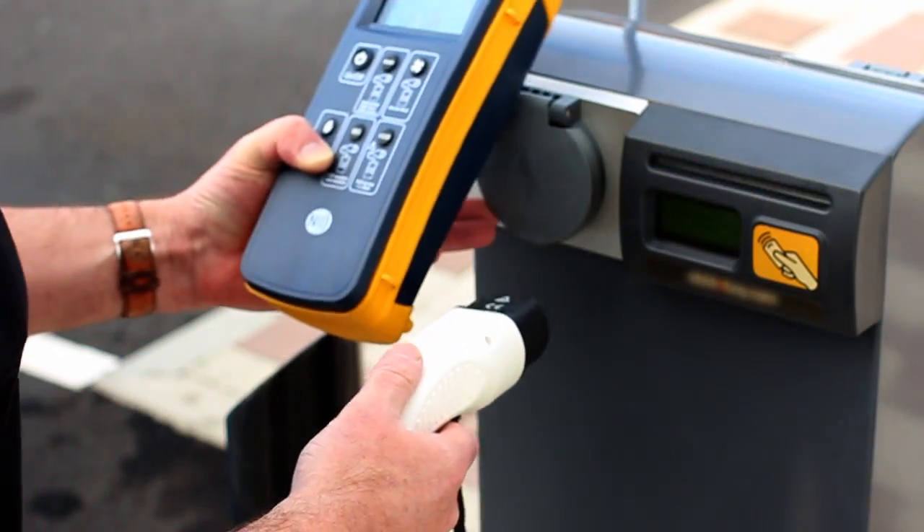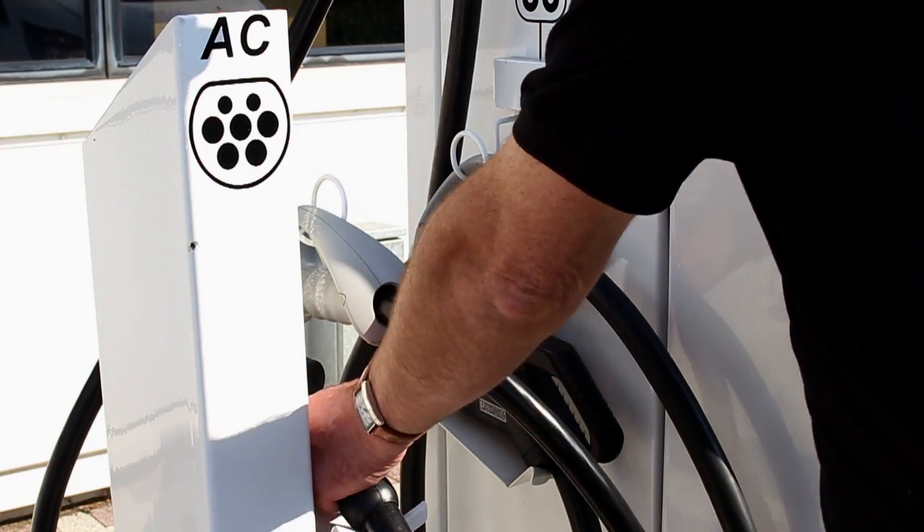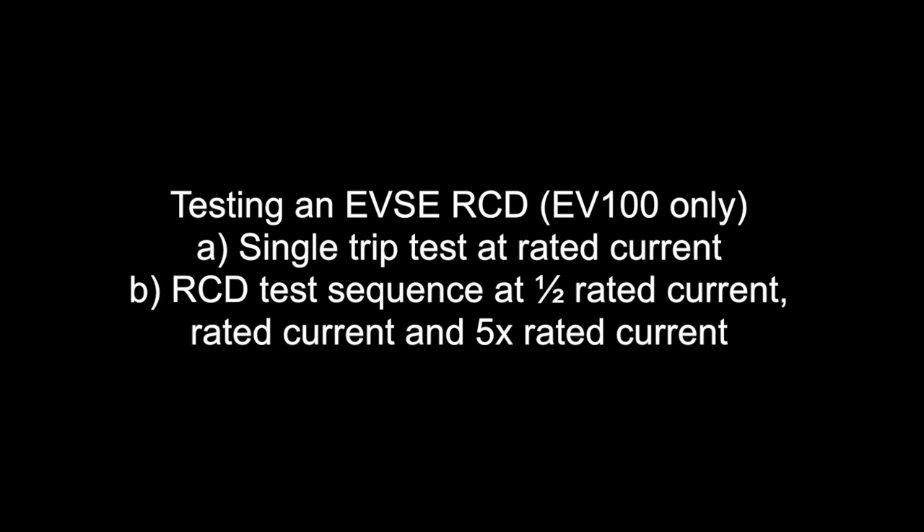The following tests can be conducted on AC EVSE with a Type 1 or Type 2 socket, or one with a tethered cable using the special test adapters. There are two options when testing an EVSE RCD using the Seaward EV100: the first is the single trip test at rated current; the second is an RCD test sequence at half rated current, rated current, and five times rated current.